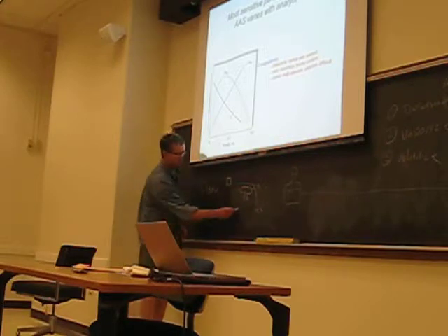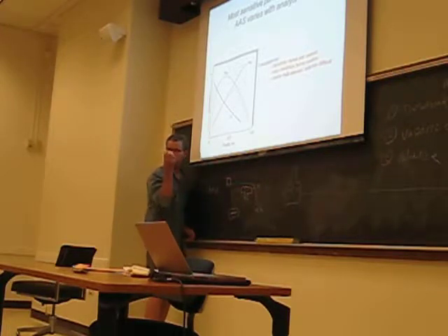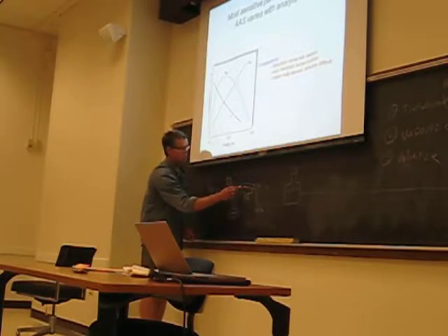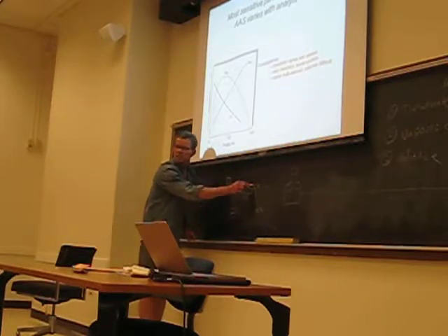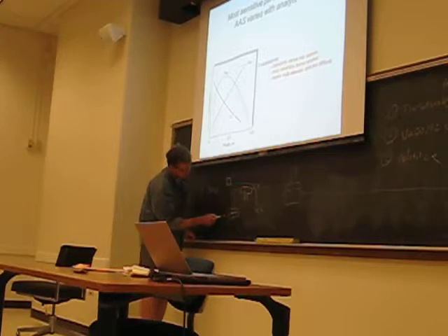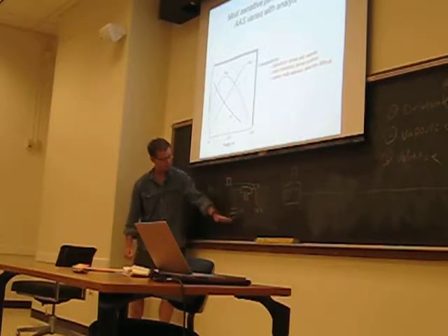And the whole idea is that if you look down on the burner head with a slot like this, you want the light beam, which is probably about as thick as this piece of chalk, to be perfectly parallel to the top of this burner, so that the thermal zone of the flame that it's passing through is equal across the entire burner surface. And you want obviously to be exactly on top of that slot, right? So you rotate this way and up and back, and do that way.